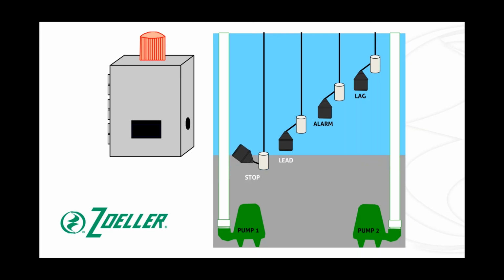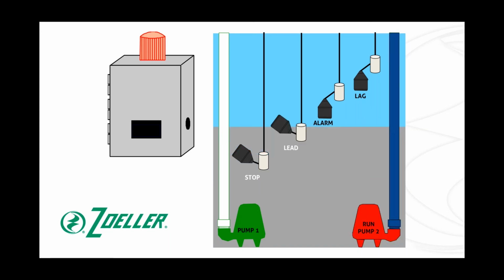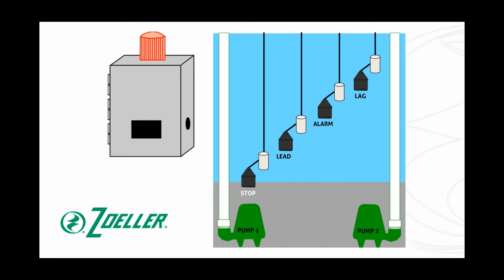So here we go again. Water's coming in. Stop float goes up. The lead float now goes up. When the lead float goes up, again, it's going to call for the other pump, or whichever one is next in line, our lead pump, to come on. In this case, it's pump 2. Pump 2 begins pumping and discharging water. As pump 2 discharges the water, it's going to again run until the stop float drops out and shuts the system off and again, ready for another pumping cycle.